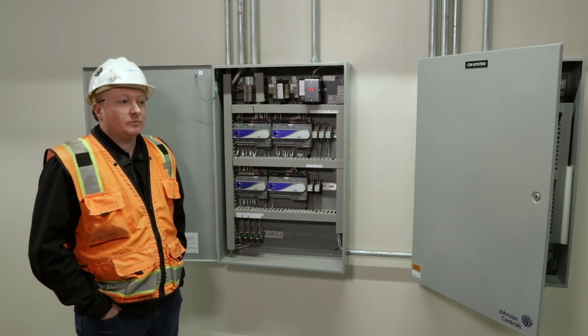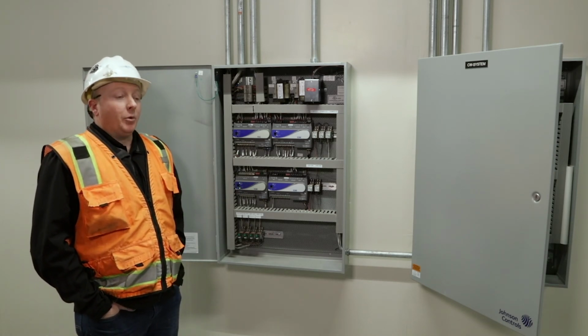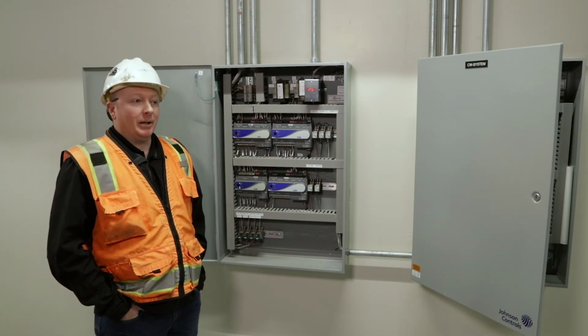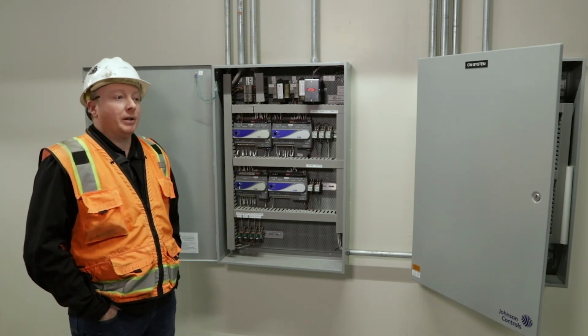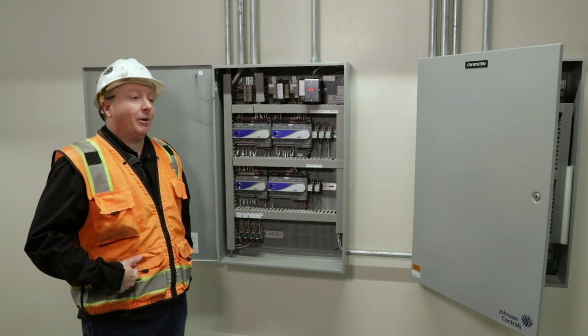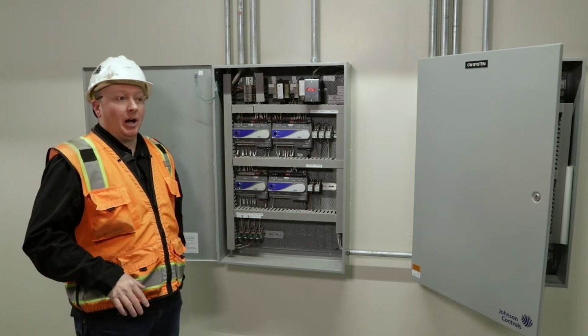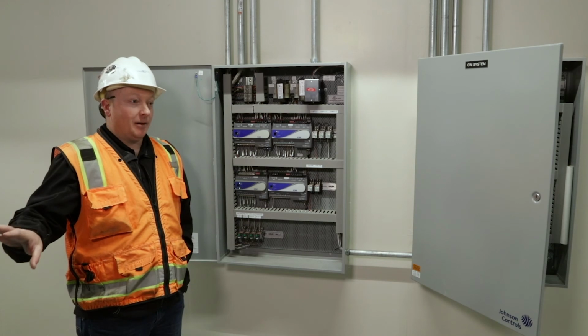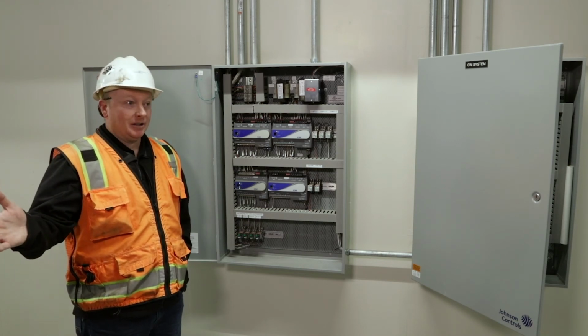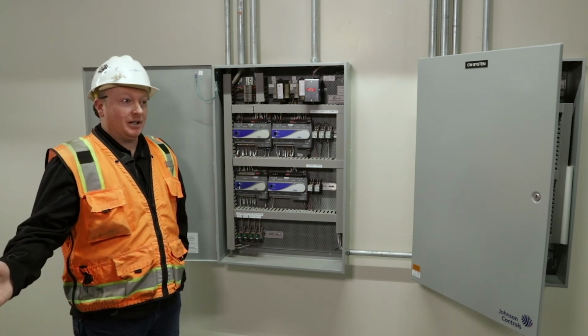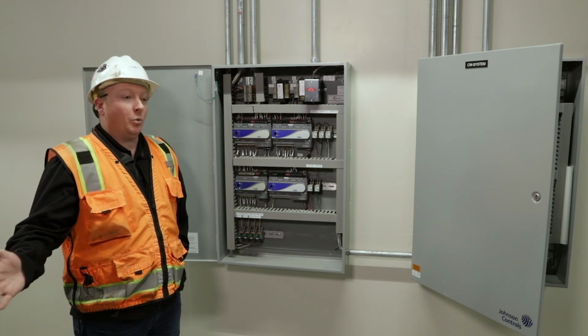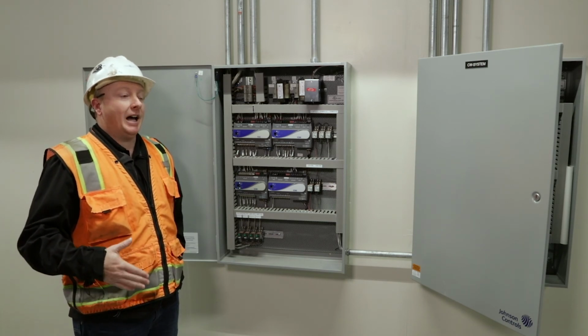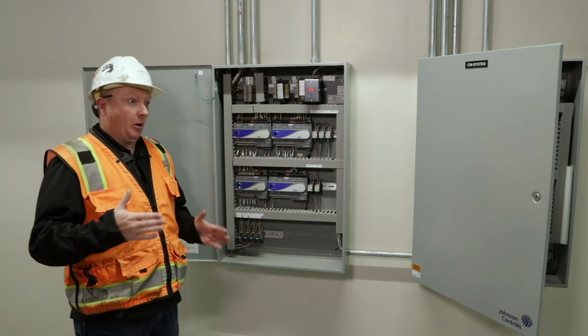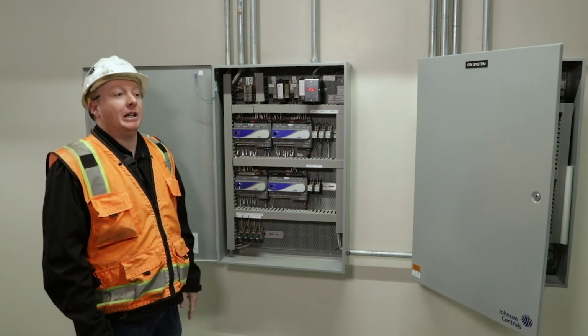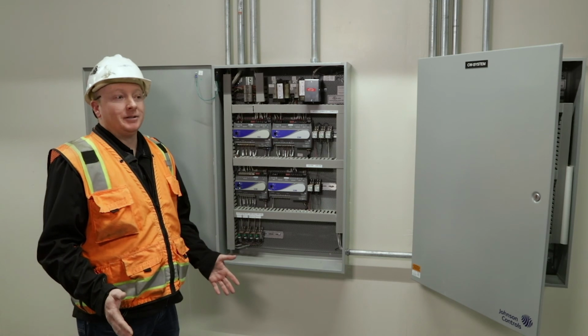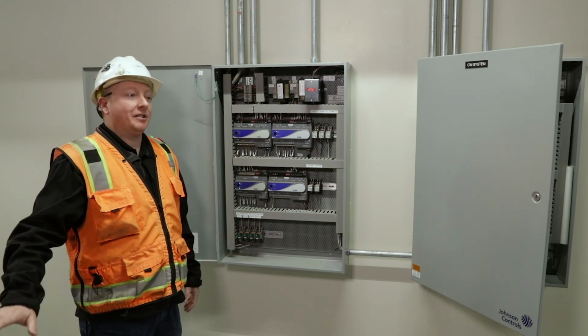So how is it staged again with the chillers? Is it lead lag? It's runtime. So when the plant is enabled, it'll just pick the one with the lower runtime. And we're calculating that runtime on the BMS. We're not getting a real runtime value from these chillers. So obviously the existing chiller has more runtime than the York does, but we're just totalizing the status or our command to these chillers starting, since we brought this online. So they both started at 0 on our system. We know in reality that's not the case.